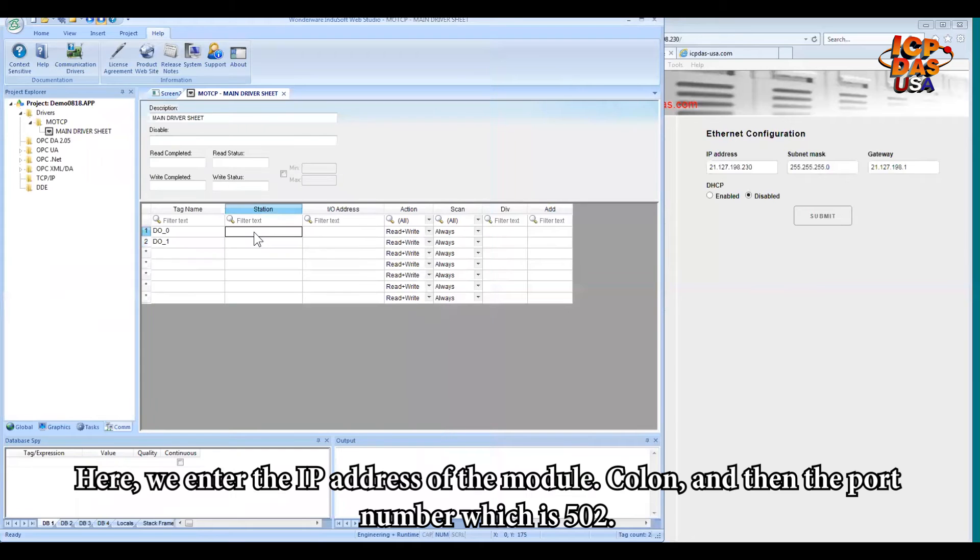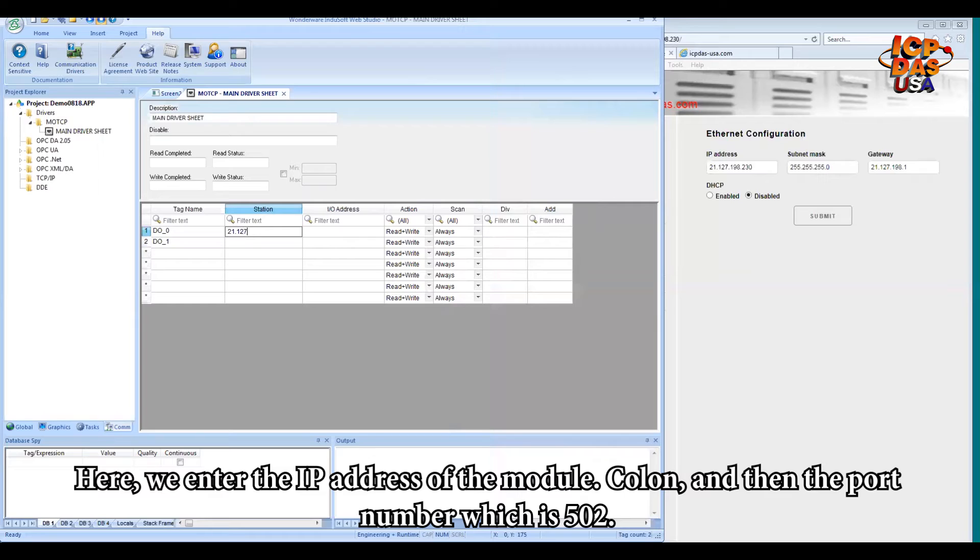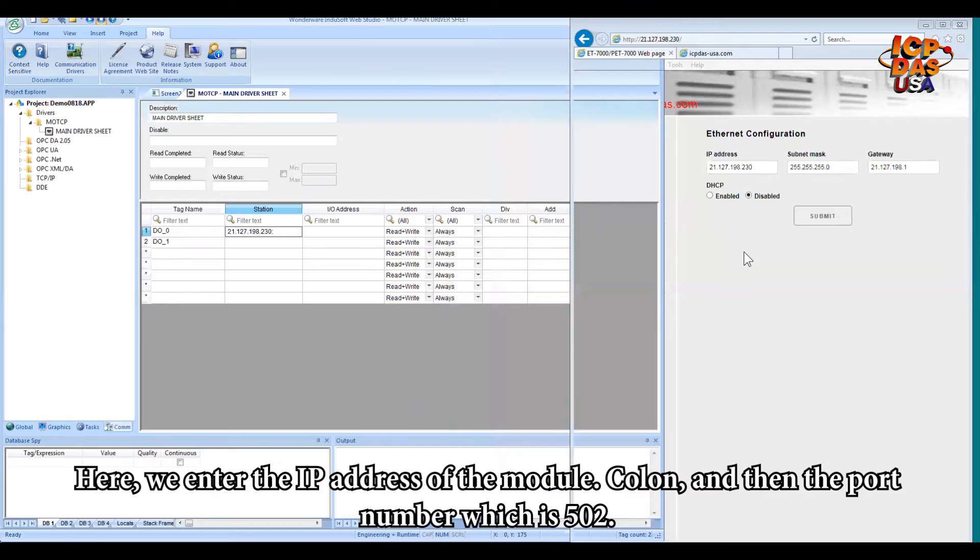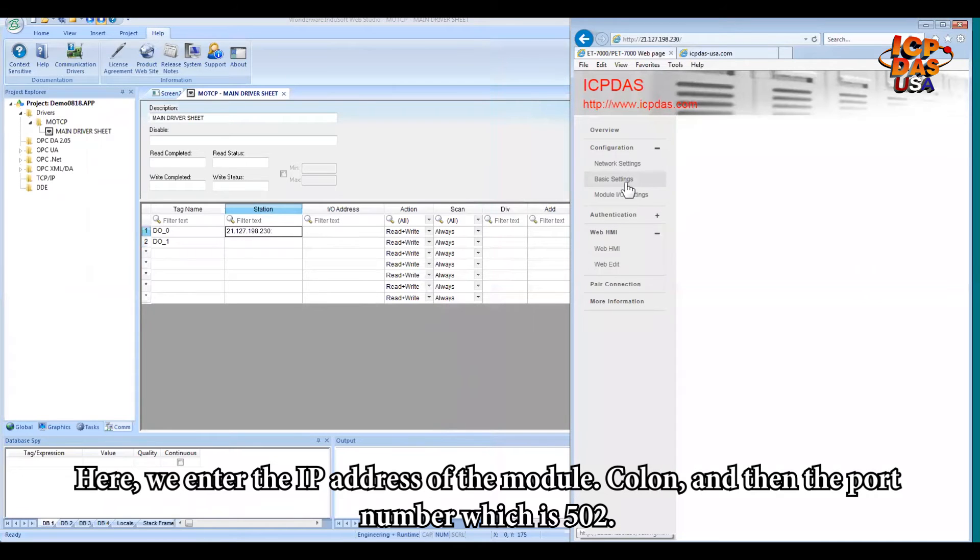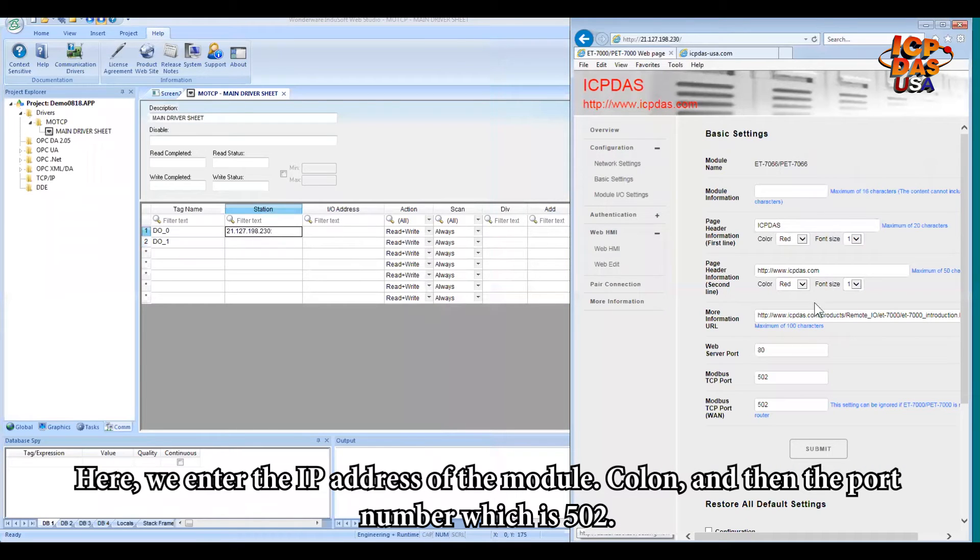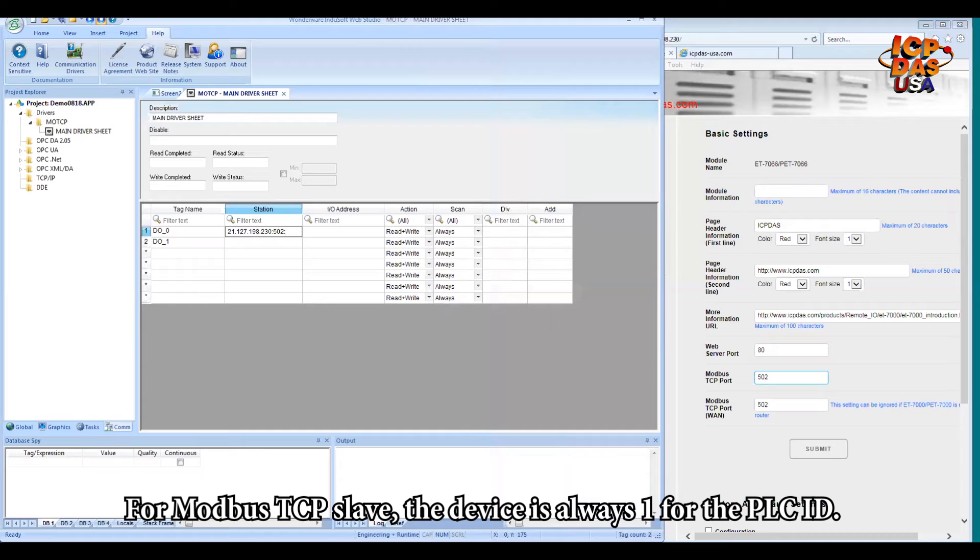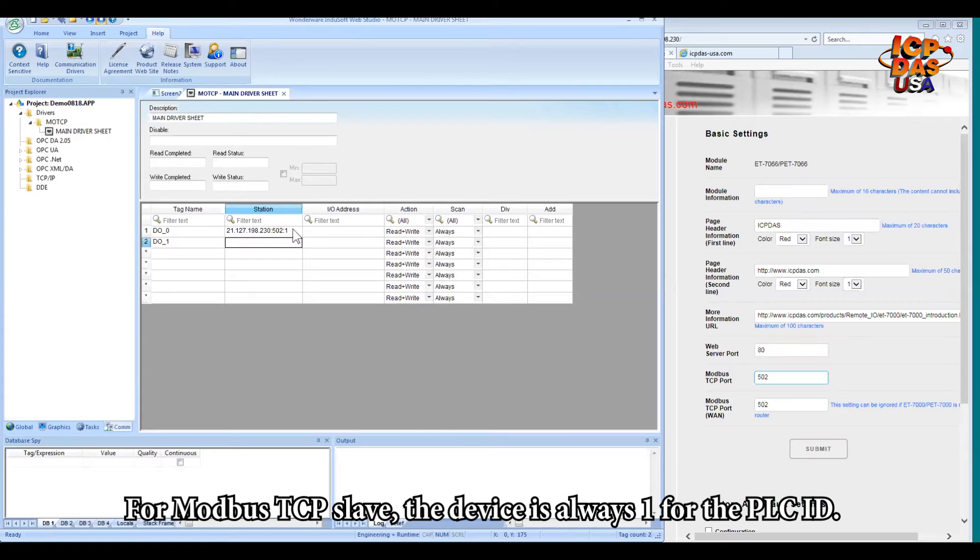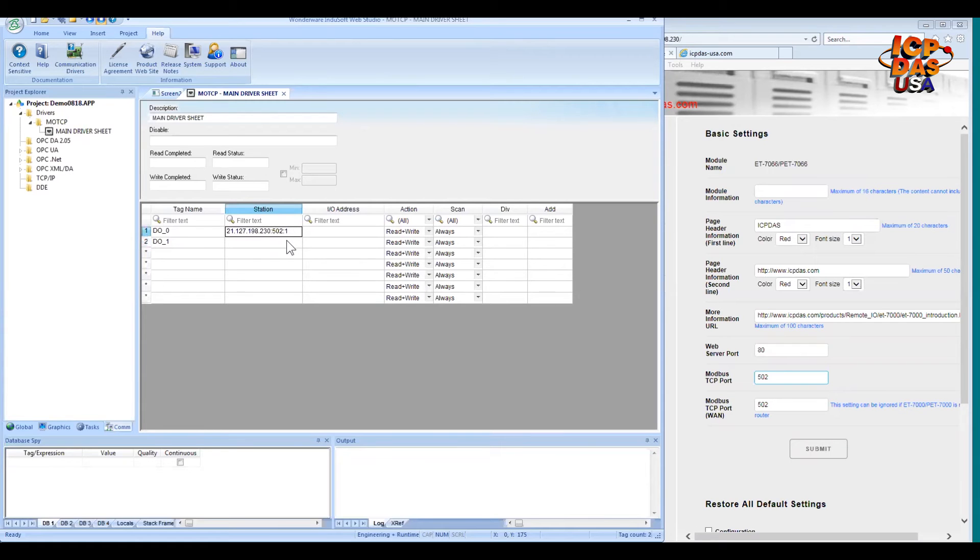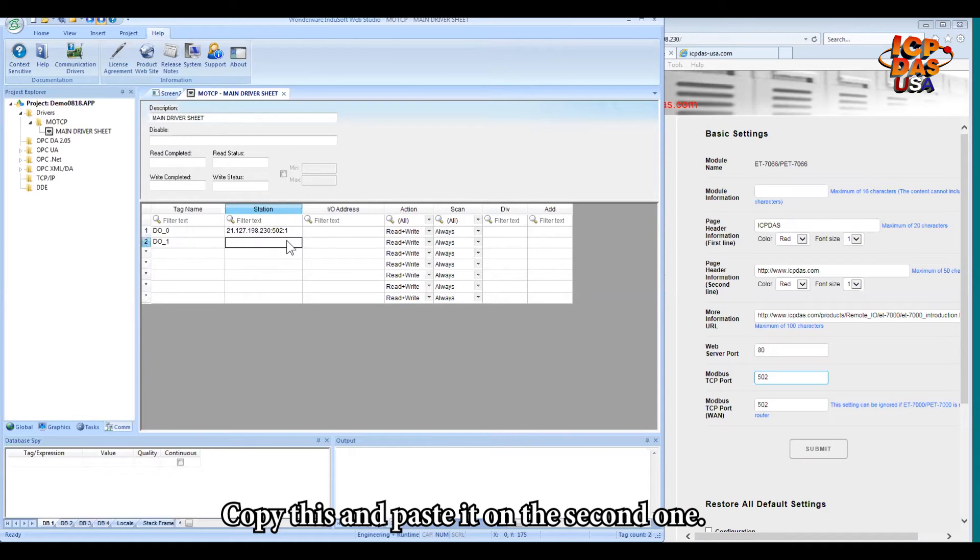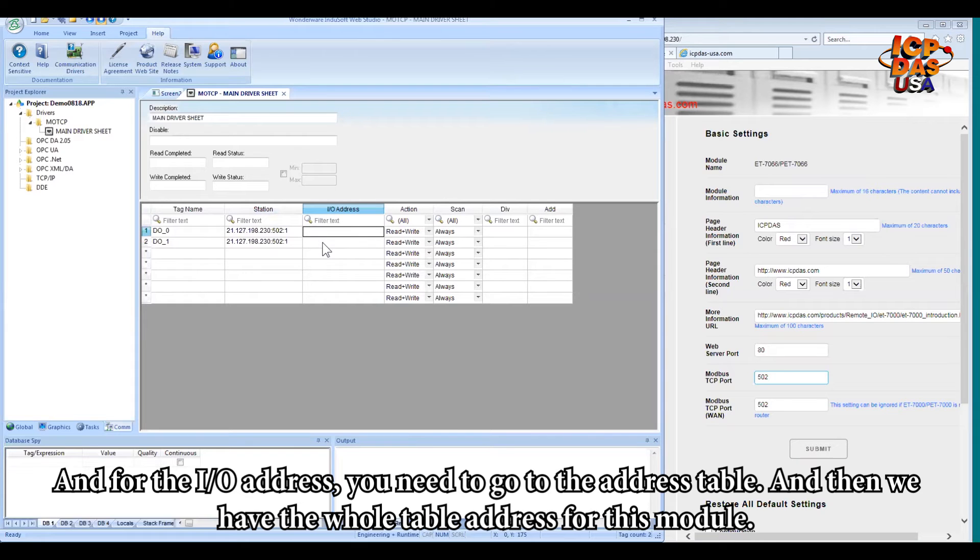So here we will enter the IP address of the module, which is 21.127.198.230, colon, and then the port number, which is 502. This one is the Modbus TCP port number, 502. So for Modbus TCP slave device, there's always one for the PLC ID. Copy this and place it on the second one.